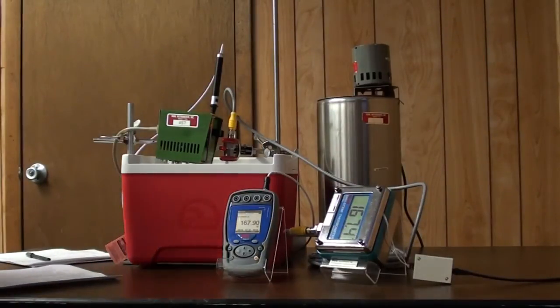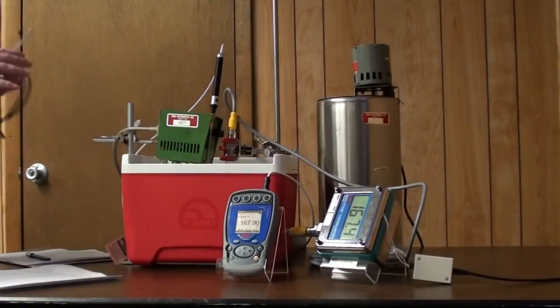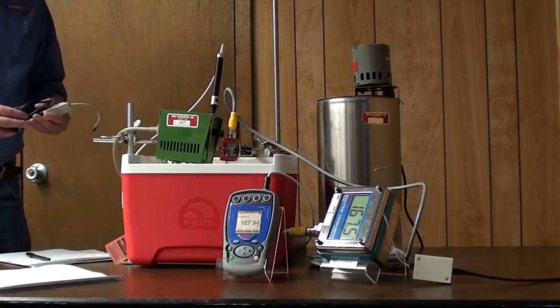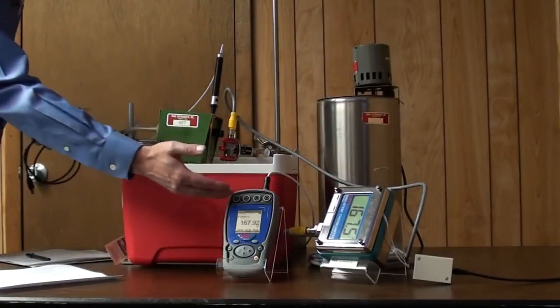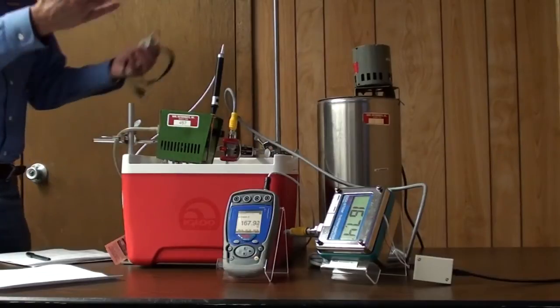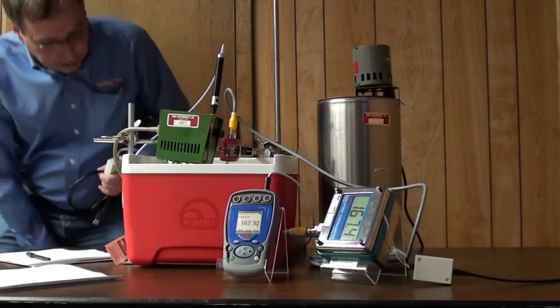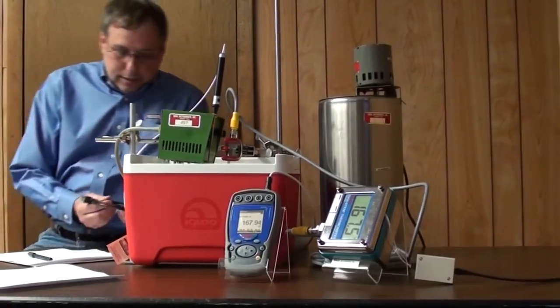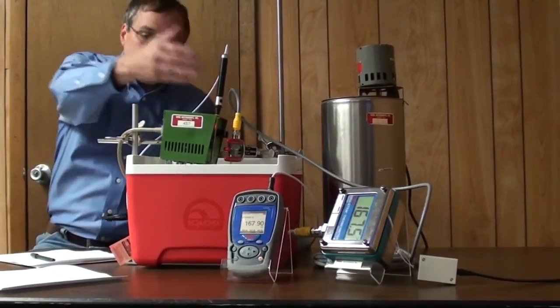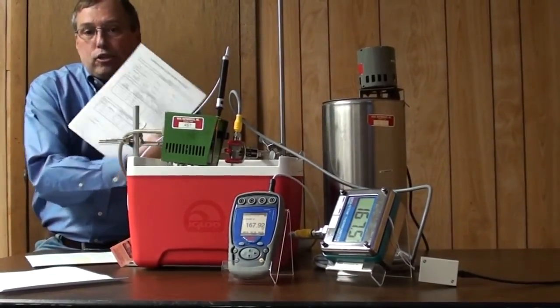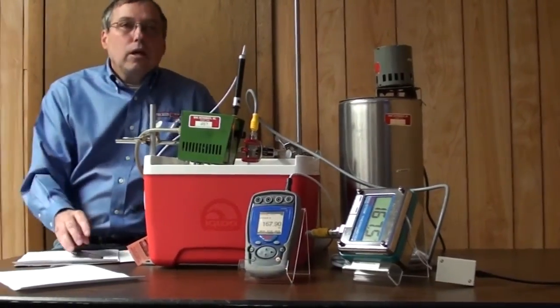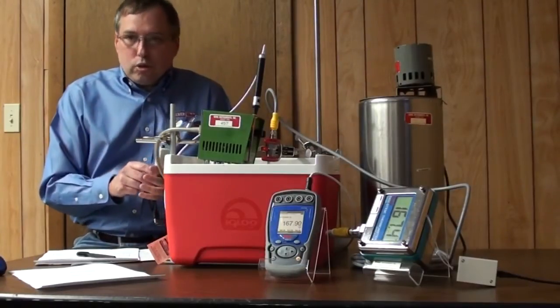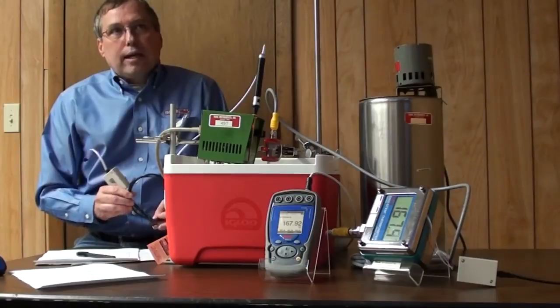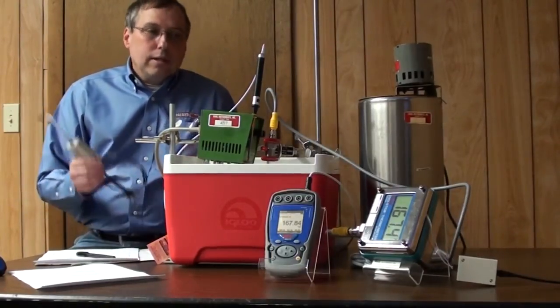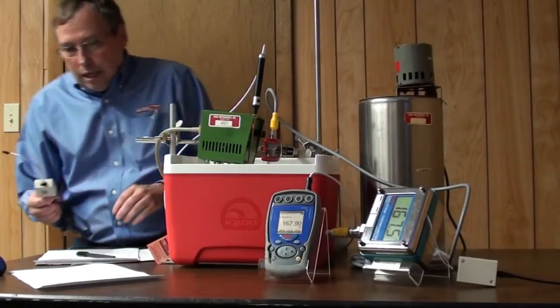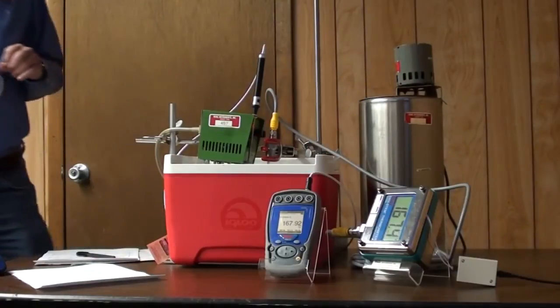if you're doing calibrations and you buy DST Cal, you only need that if you're going to make adjustments to the unit. To do calibrations and check the accuracy, you need a standard instrument and baths, and certainly water you can't use at processing temperatures. So we would use oil baths, and with an oil bath, a standard instrument like this, and a form, you can do your calibrations. If everything's in tolerance, you're good to go. If it's out of tolerance, or you want to try to get it a little closer or make adjustments, our calibration software also associates the probe and lets you change the refresh rate, things like that. So that's our option, DST Cal, is what we call it.